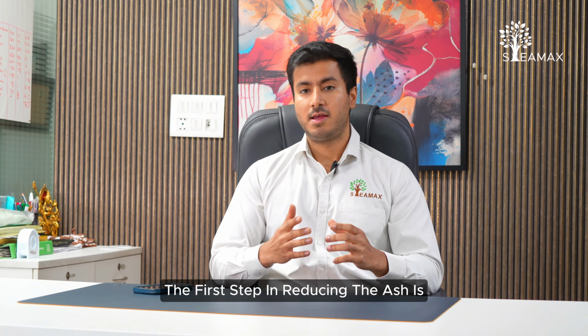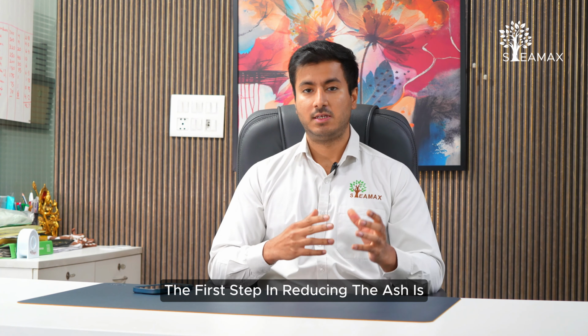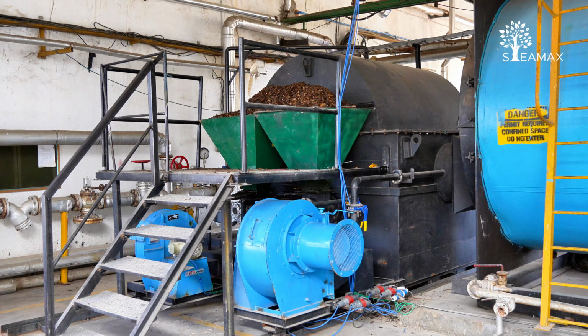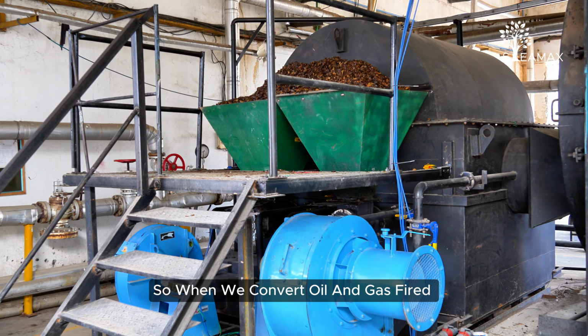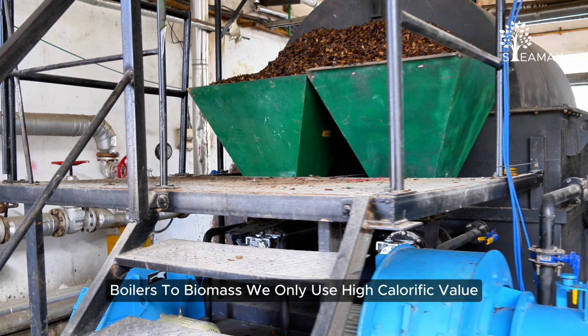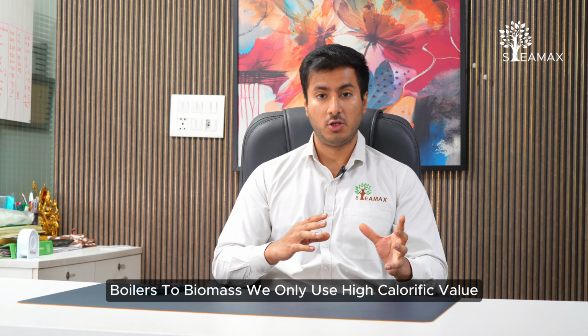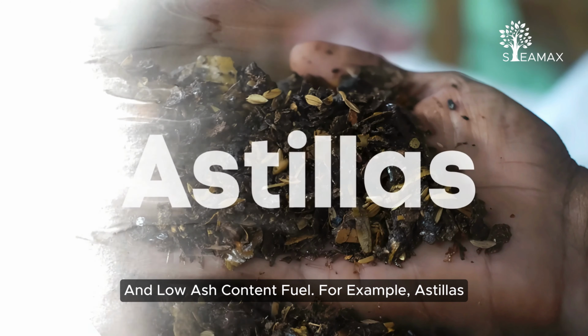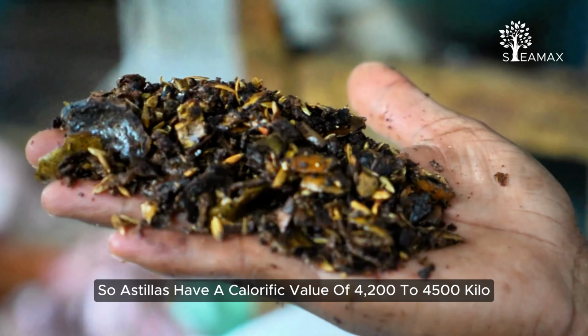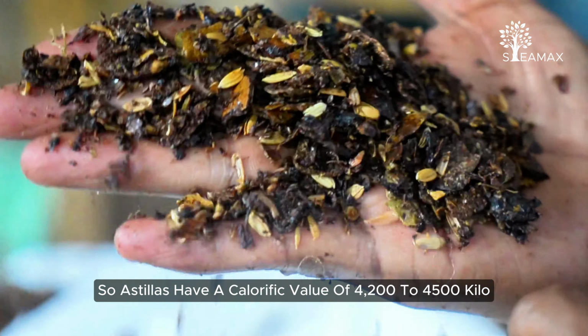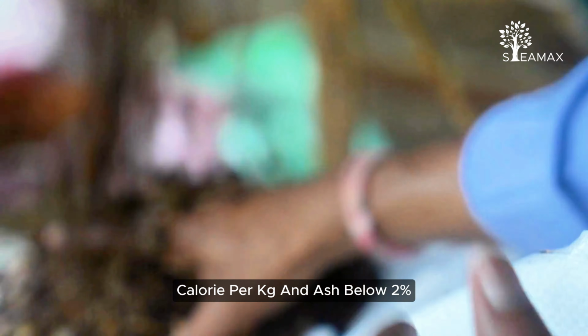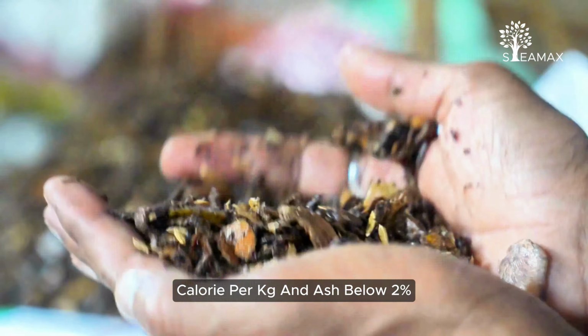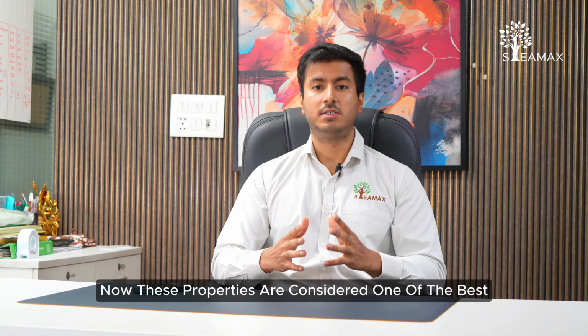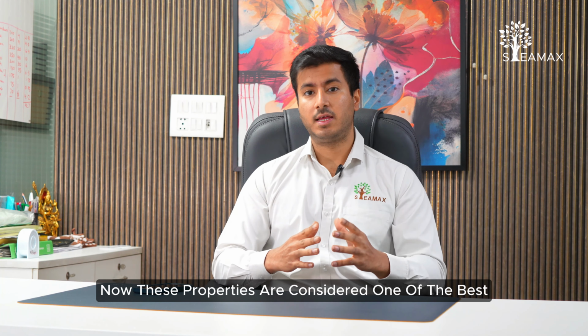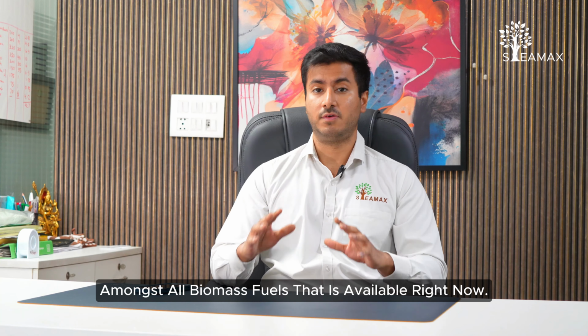The first step in reducing the ash is selecting the right kind of fuel. So when we convert oil and gas fired boilers to biomass, we only use high calorific value and low ash content fuel, for example, Astillas. Astillas has a calorific value of 4200 to 4500 kilocalorie per kg and ash below 2%. These properties are considered one of the best amongst all biomass fuels available right now.